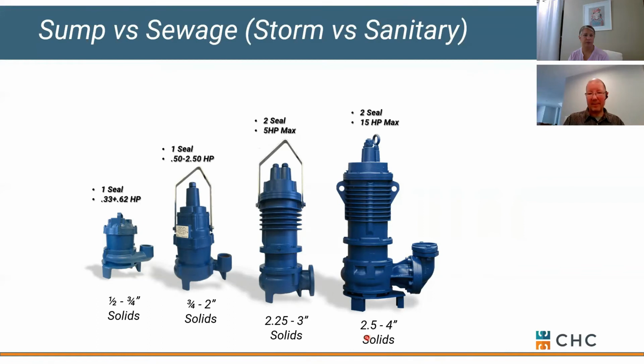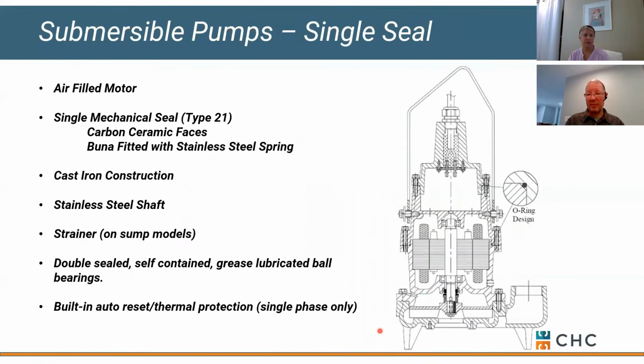So what are we talking about there? Well, a single seal pump means there's only one mechanical seal inside that pump or that housing. And if the seal fails or ruptures, guess what? We're flooding our motor. And as a result, that pump is no longer able to work for us. Okay, that's a bad day. You would tend to use a single seal pump on a pump that's going to see maybe some intermittent use, like an elevator sump. But you wouldn't put this into a typical application where you need a reliable pump to run 24/7, 365. Okay, so this would be an intermittent use.